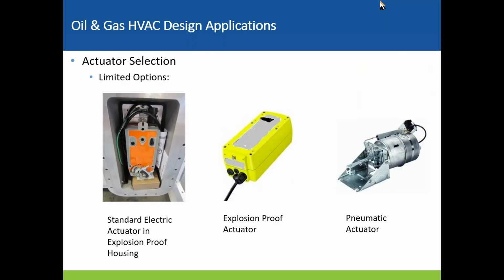And we have our actuators. This will be dependent on your client and what your situation is, if you have an instrument air system or not. So the original standard when I came into this side of the industry was we put a general purpose actuator in this big explosion-proof box, and then mount it to the side of the air handling unit or damper or whatever that may be. Fairly recently, probably in the past 6 or 7 years, we've shifted into doing more of these self-contained explosion-proof actuators. These are electric. Pneumatic is still really common in the big central processing facilities or gathering centers. So you're aware of the options that are typically used.